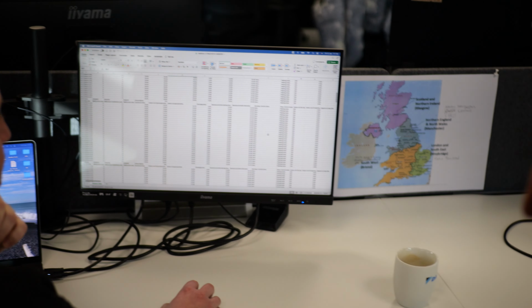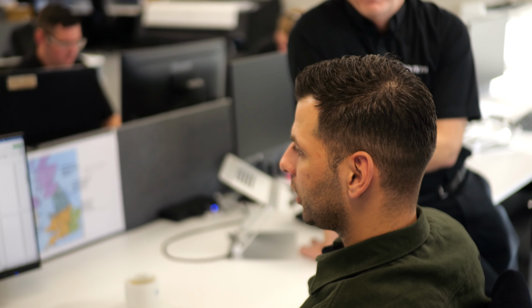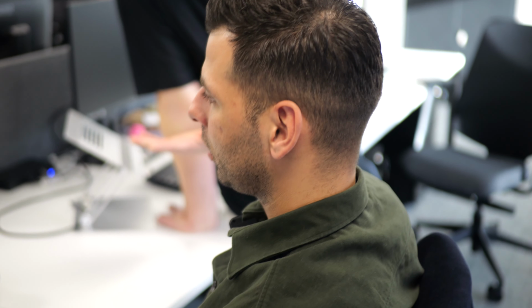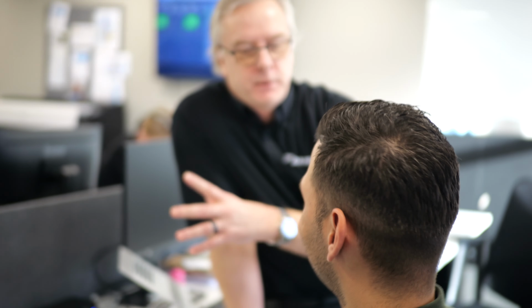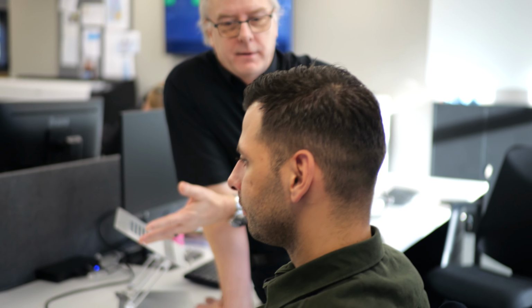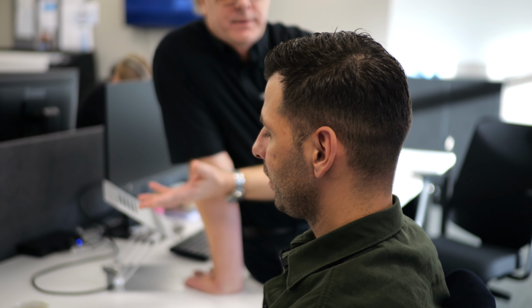This is a lot of data. This is a really good system. Almost to the stage where you think that if you've got a multi-VRV site, you'd be stupid not to have this installed, because it's quite cheap. If you've got, say, 10 outdoor units, the actual cost to monitor becomes minuscule. It will also give you the Airnet number. So if it's an indoor unit, for instance, that goes into fault, it'll tell you that Airnet number in that data. You look to the Airnet number, and then you've got the indoor data. You can see the issue.